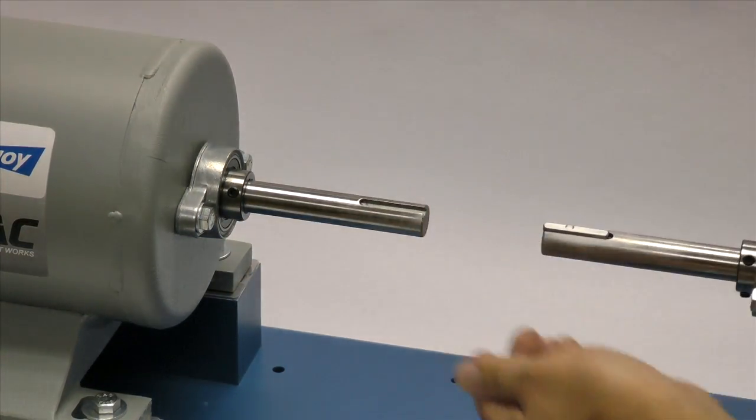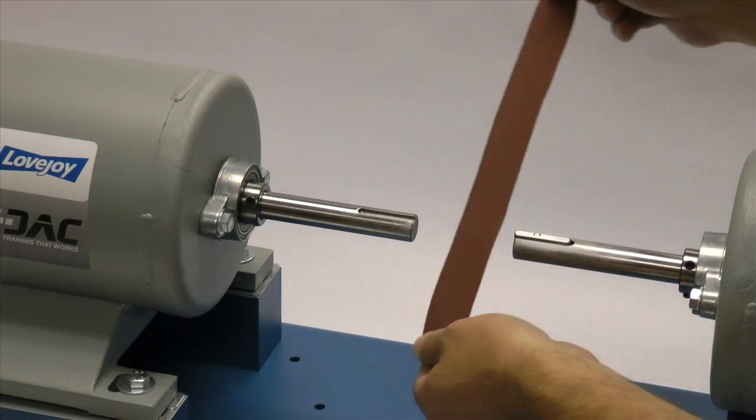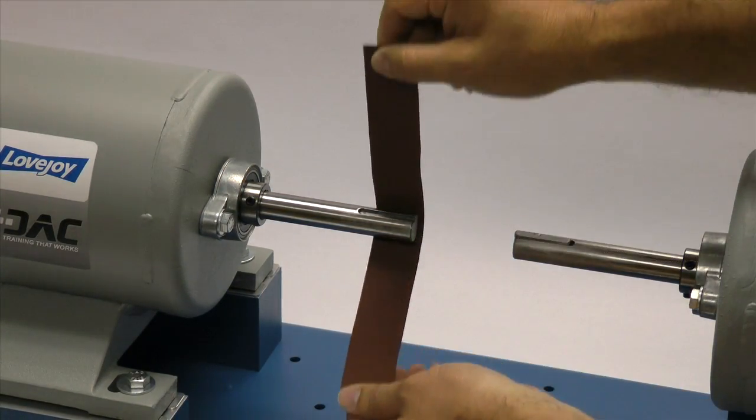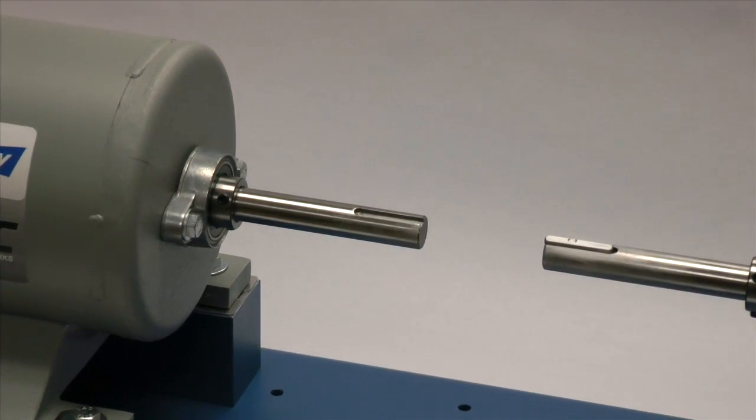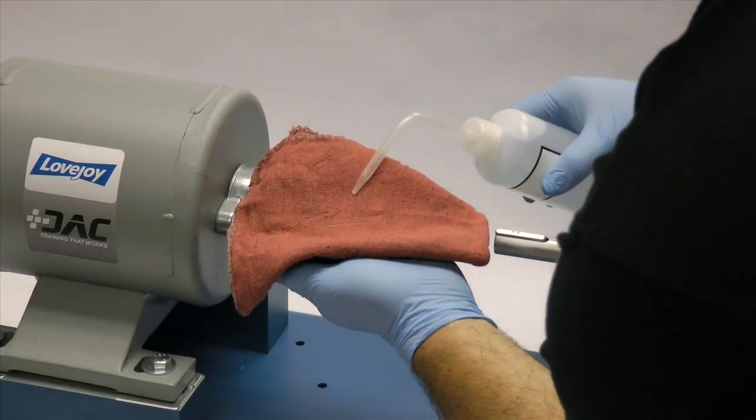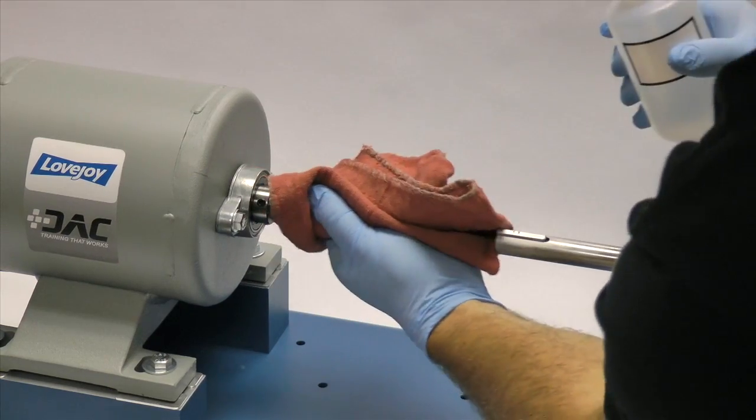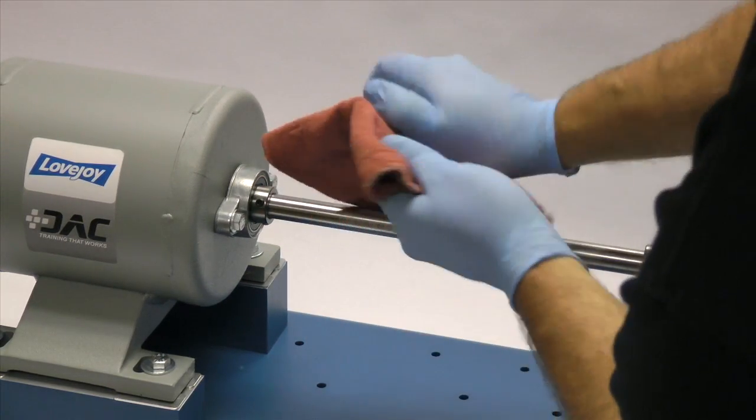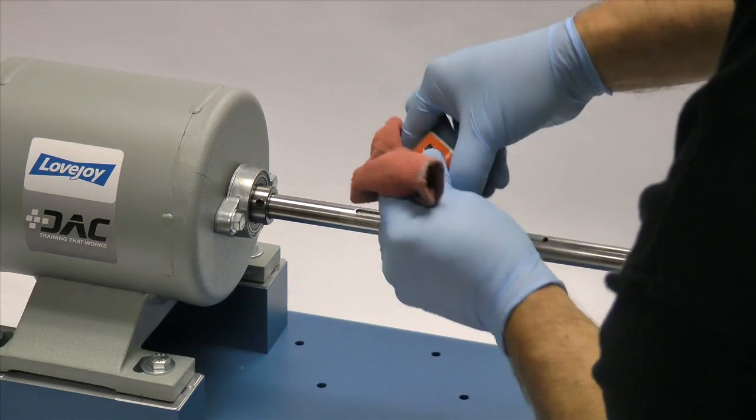A fine tooth file can be used to clean burrs from the edge of the keyway or large dents in the shaft. The emery paper can be used to clear the shaft of rust or any fretting corrosion. Finally, using our cloth and cleaning solvent, we need to ensure the surface of the shaft and the keyway are clean and free of dirt. The hub should also be cleaned to remove any coatings used to protect them during shipping.